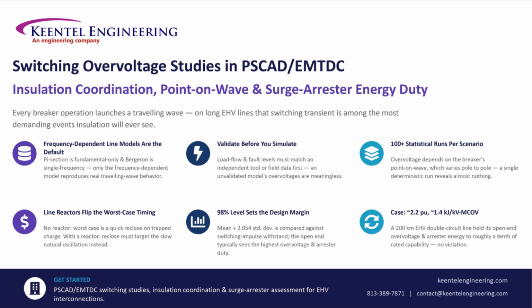Line reactors actually flip that worst case entirely. Without one, it's a fast reclose onto trapped charge. With one, it's timing the reclose against the line's own slow natural oscillation. In one real EHV case we ran, a 200-kilometer double-circuit line held its overvoltage and arrestor energy duty to roughly a tenth of rated capability with no violation.